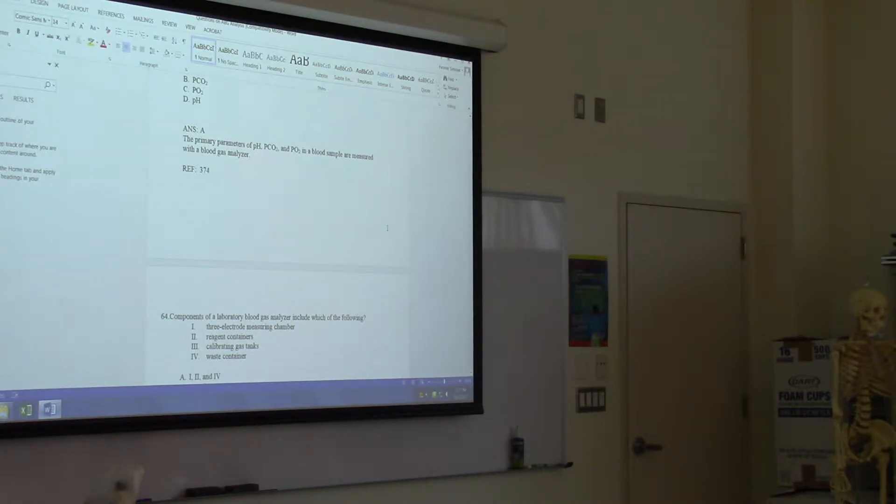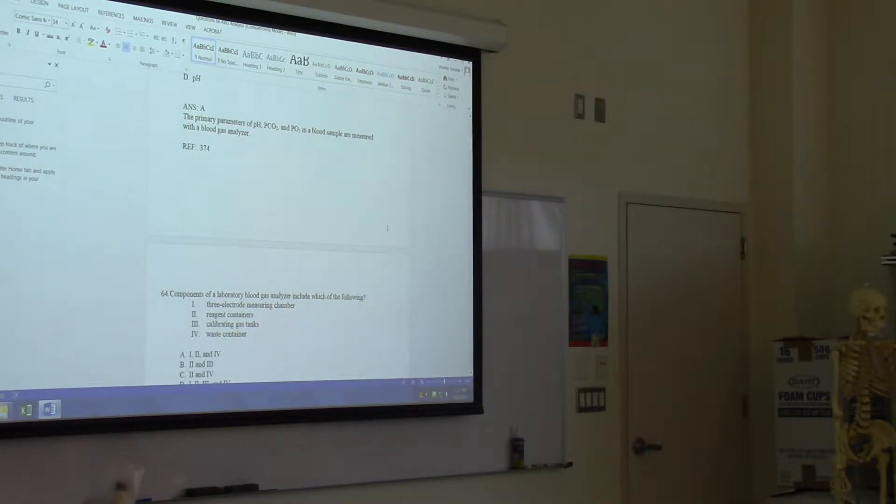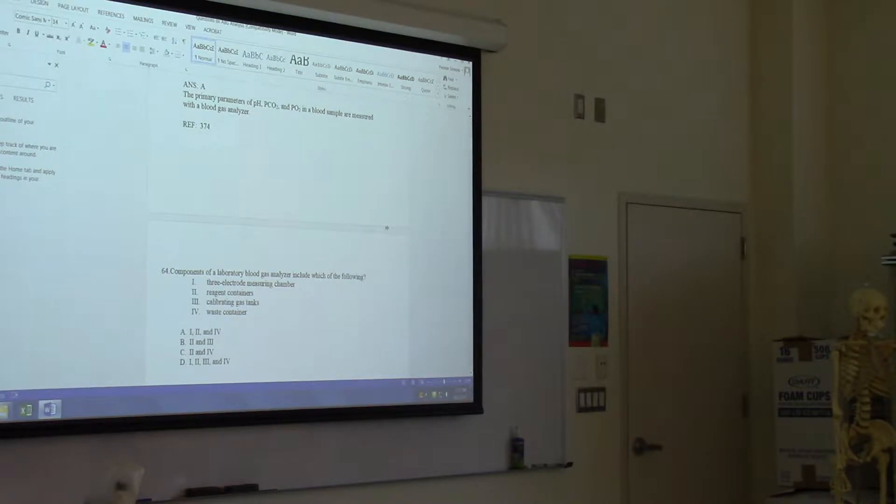Components of a laboratory blood gas analyzer include which of the following: three electrode measuring chamber, reagent buffer solutions, calibrating gas tanks, waste container. D, letter D.